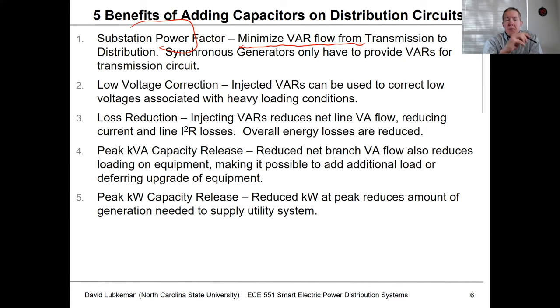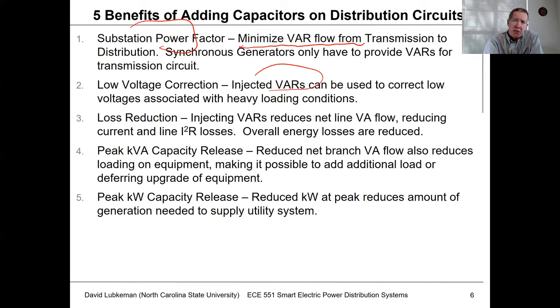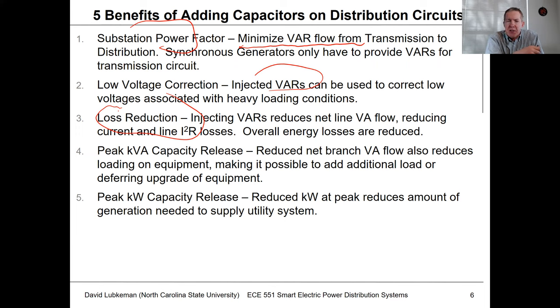The second benefit is controlling voltage — specifically keeping it from becoming too low. By injecting VARs, we can actually boost voltage, so a heavy loading condition that pulls voltage down gets boosted back up. The third benefit is loss reduction: if we provide VARs locally, we don't have to transmit reactive power over lines and transformers, which keeps current magnitude down and reduces I-squared-R losses.